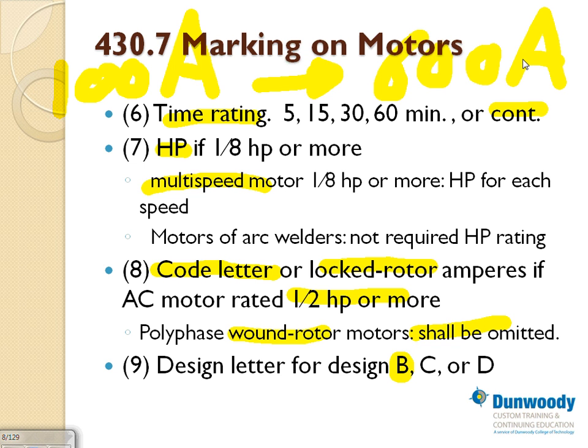Design B, C, and D, if you're familiar with them, guys. Motors are mechanical machines. What do we use motors for? We use them to drive mechanical equipment. Now, the mechanical equipment has mechanical loads in it, and the mechanical loads are different. A motor that drives an elevator is different than a motor that's driving a conveyor. It's different than a motor that drives an air handling unit fan. So based on the function of the mechanical load, you need to match it with a design.